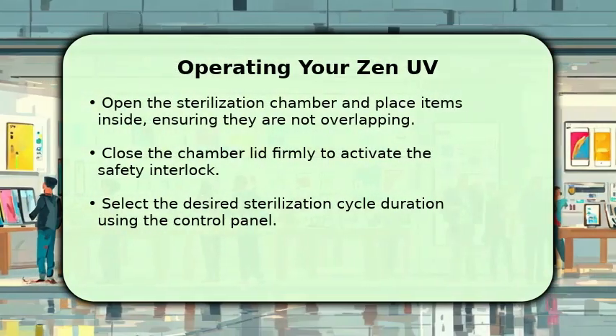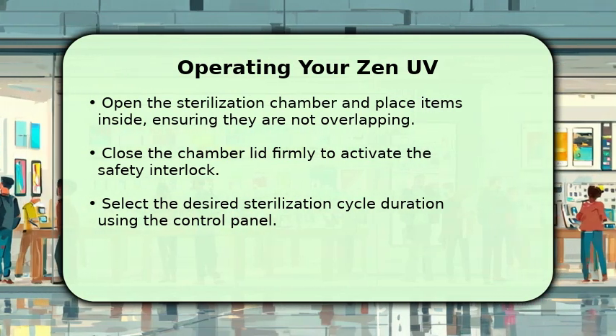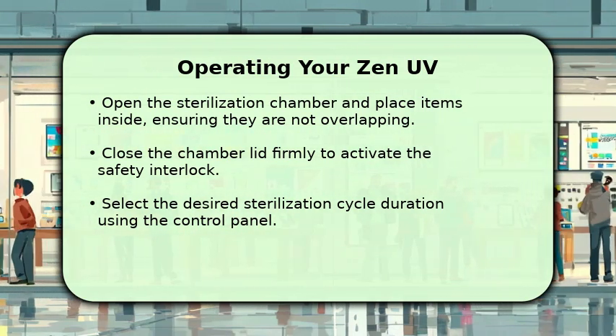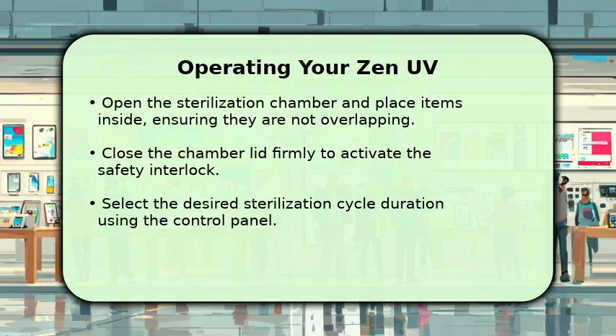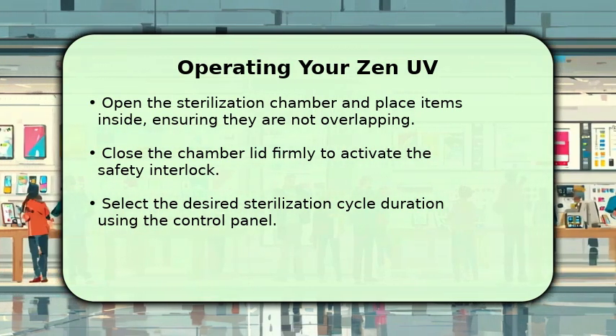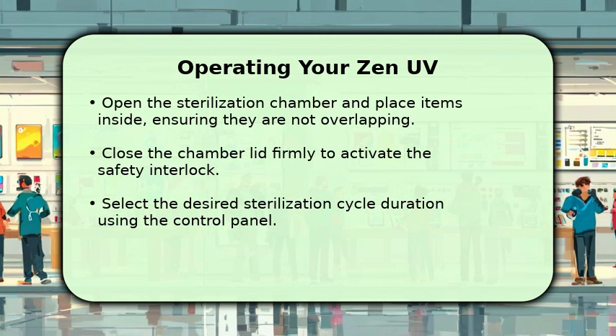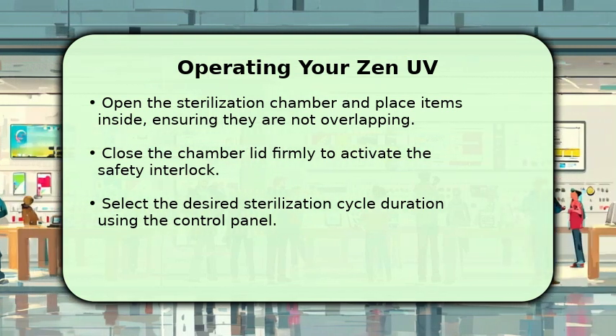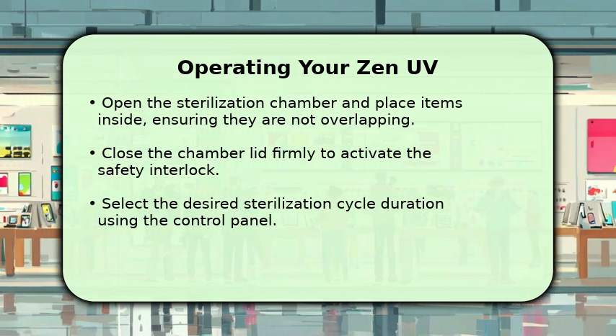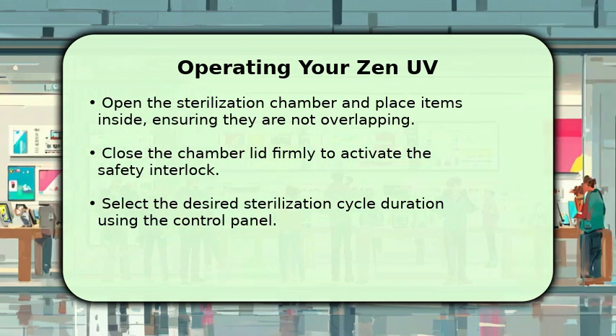To begin operation, gently open the sterilization chamber and arrange your items inside, making sure they do not overlap. Overlapping items can reduce the effectiveness of the UV light. Firmly close the chamber lid. A click indicates the safety interlock is engaged.